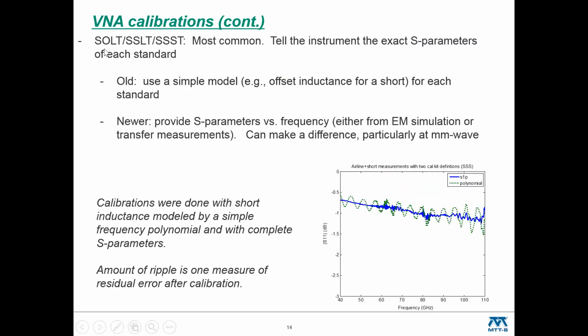Open-short-load is probably the calibration method people are most familiar with, and it has some friends based on offset shorts in a load, or just offset shorts. The premise of these techniques is you tell the instrument exactly what the S-parameters are of each standard, and the instrument will do what it has to in order to reproduce those values it's told. As a sidebar, that makes using one of these standards as a verification device not terribly productive, since the VNA is just going to try to reproduce what it was told.